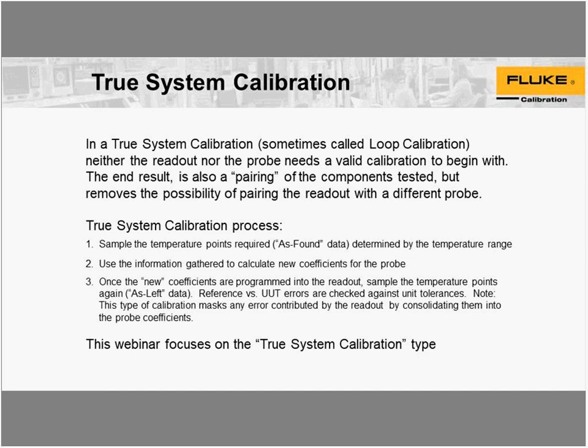System calibration or loop calibration is what we're going to focus on today. What it consists of is, again, we will bring the units together, making as found data. We will not separate the units. We at that point evaluate the data, determine if we need to run an annealing process, or if we can go ahead and align the units, and then take as left data.